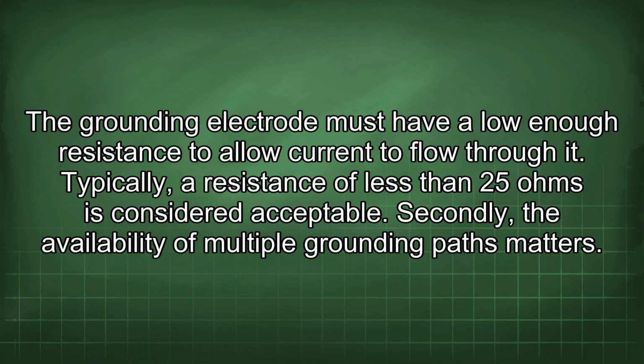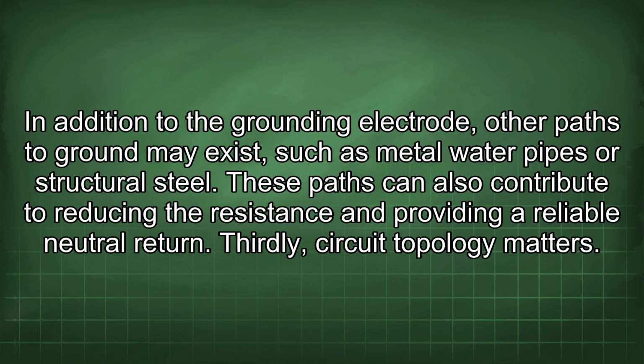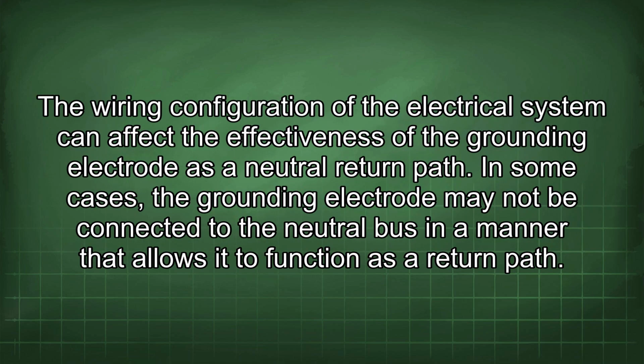Secondly, the availability of multiple grounding paths matters. In addition to the grounding electrode, other paths to ground may exist, such as metal water pipes or structural steel. These paths can also contribute to reducing the resistance and providing a reliable neutral return. Thirdly, circuit topology matters. The wiring configuration of the electrical system can affect the effectiveness of the grounding electrode as a neutral return path. In some cases, the grounding electrode may not be connected to the neutral bus in a manner that allows it to function as a return path.